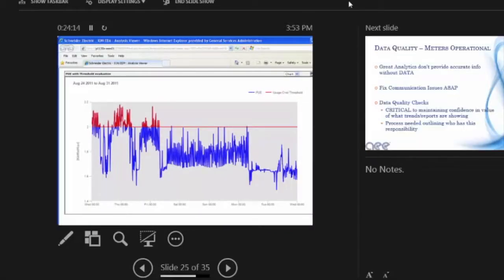This is a data center. We were calculating PUE, and they were trying to get it below a certain threshold. They wanted to have it below this threshold here, so it would go red if it went above. It would stay blue as long as they were keeping that value low. So they had the guy in there, throughout the first few days working, moving some cabinets around, unblocking some vents, and finally found the way that would make it where they could keep it under the PUE that they wanted.